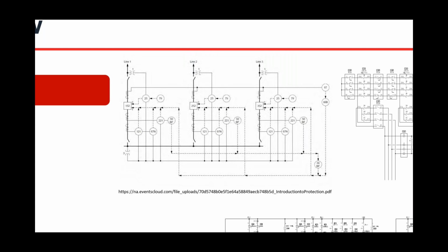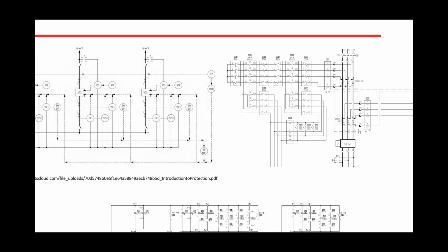If you're looking at a short circuit study, the last page, at least on the ones that I've seen, is usually a one line of the system, but that one line will tell you things like impedance and available short circuit current. This one in particular is a one line of the protection scheme. It tells you the relays and what functions are available. So being able to capture that, to see that.